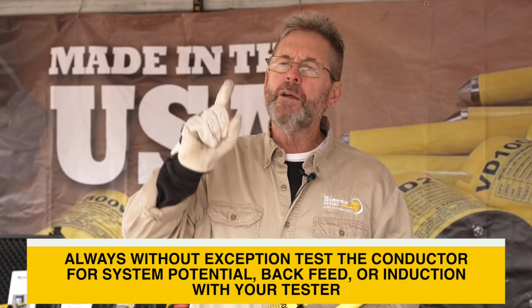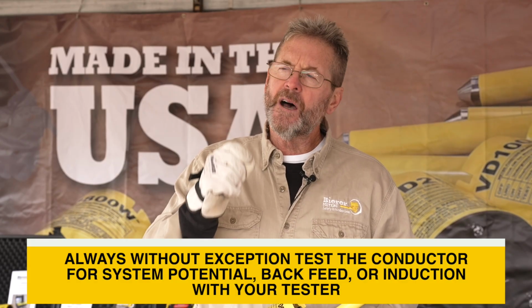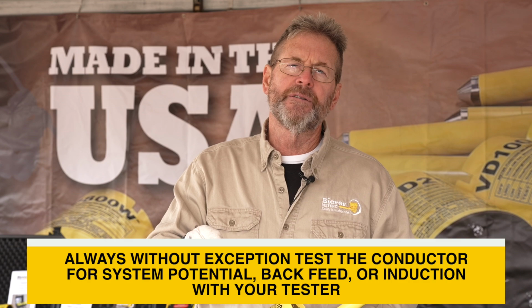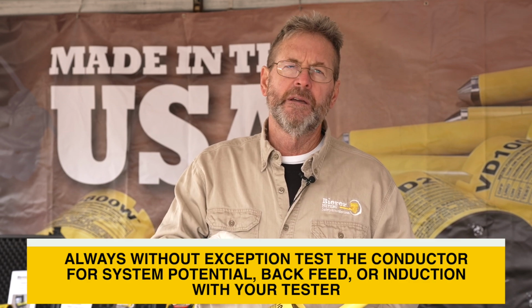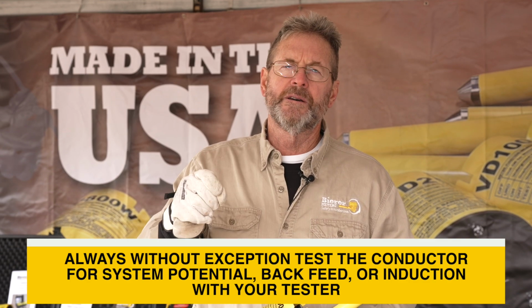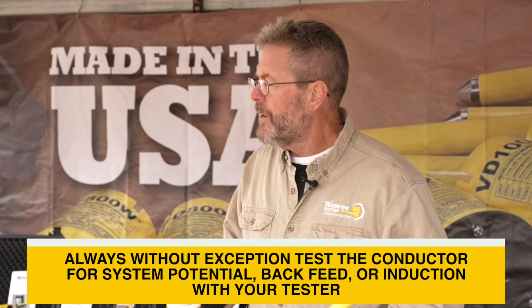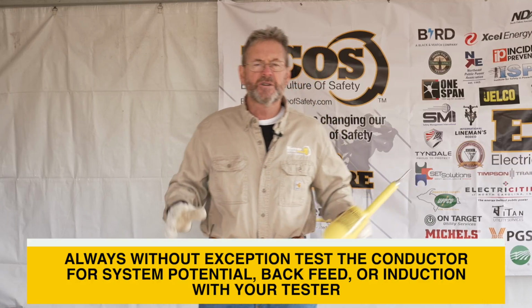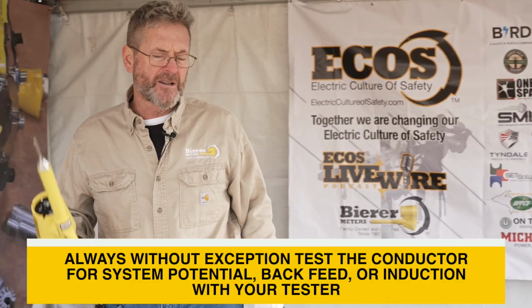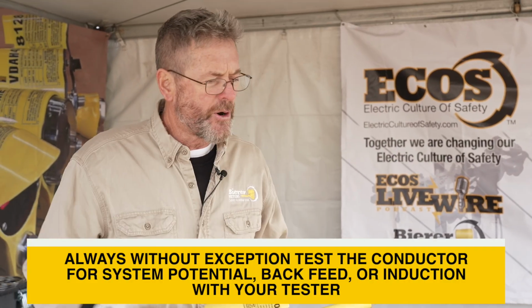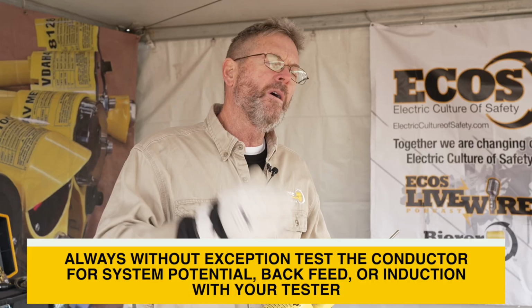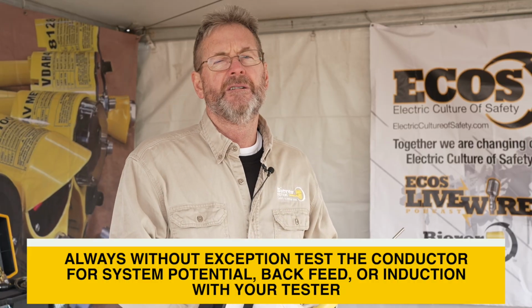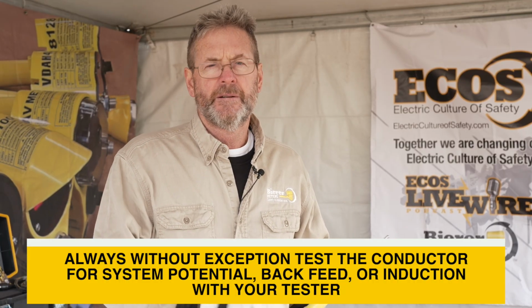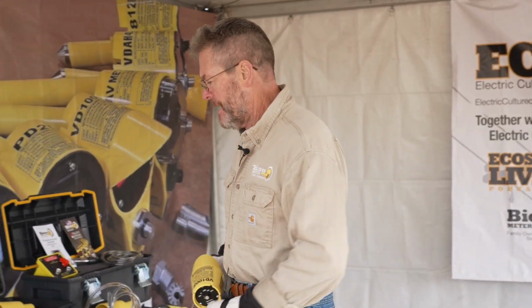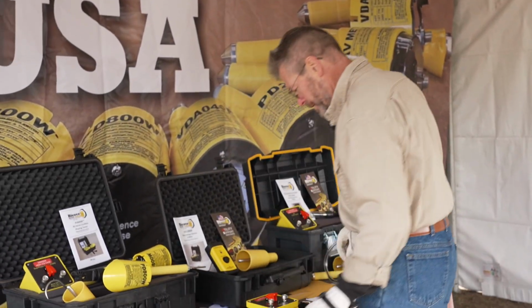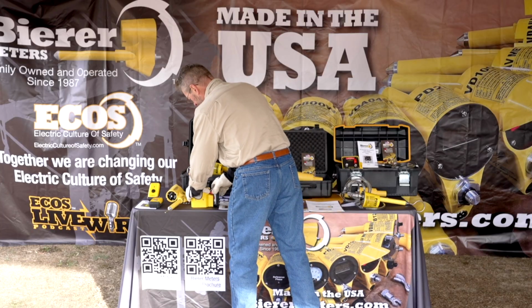No. We want you to test. Is there induction on that line that needs to be bled off? Is there backfeed? We always want you to test every single time. We do not want anybody to say, oh, it's good, I checked it, they called in, the switch is open, we're good. Always test the conductor every single time. Okay? All right. Now what we're going to do is go to our 3 kV power supply.